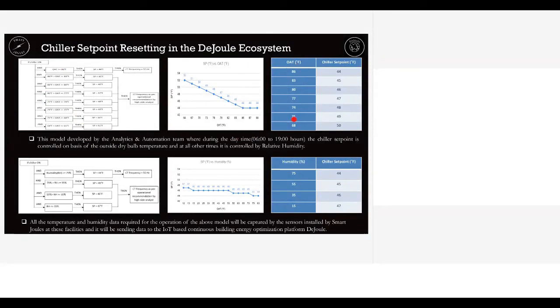So set point versus humidity, and set point versus outside dry bulb temperature - this is outside humidity based set point and this is outside dry bulb based set point. This is another way we control the system, through algorithms our people have written, changing the set point in real time. Not a person sitting in front of a computer changing the set point - 25 or 30 algorithms running in the IoT hardware on site or in the building, taking decisions in real time. That is machine-to-machine decision making on top of data.